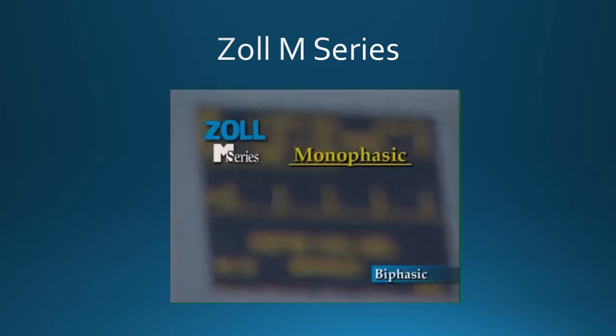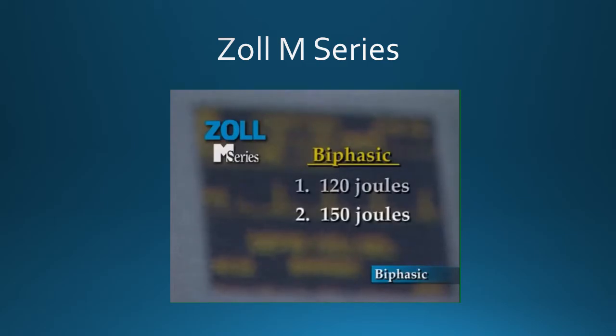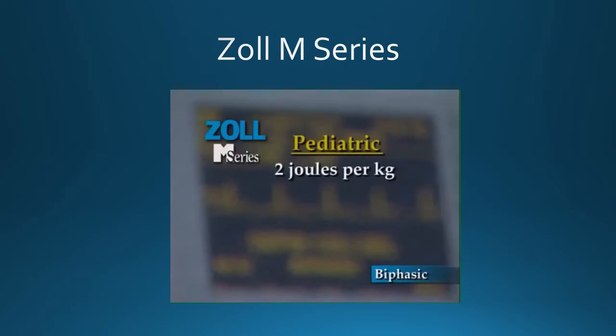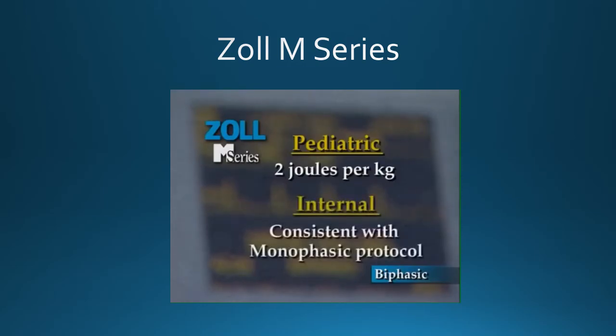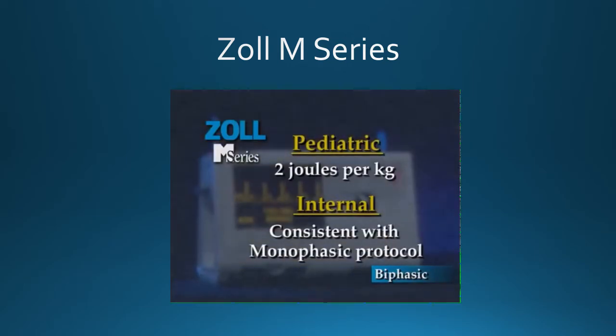The suggested 3-shock VF protocol for monophasic waveforms is 200, 300, and 360 joules. The suggested biphasic 3-shock VF protocol is 120, 150, and 200 joules. Successive low-energy shocks should remain at 200 joules. Recommended pediatric settings should remain consistent with monophasic joule settings. Users should consult your medical authority to confirm pediatric settings. Biphasic energy levels for internal defibrillation should also remain consistent with monophasic protocol, unless otherwise directed by your medical authority.